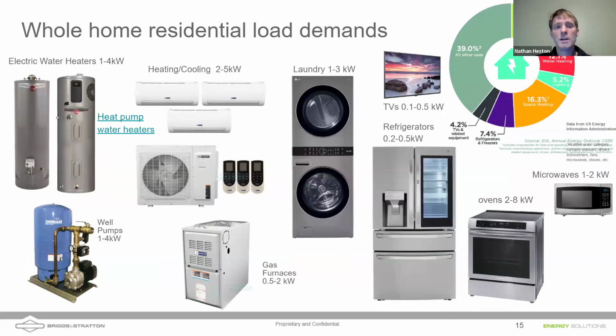cooling with electrical. The advantage of a heat pump as opposed to resistive heaters with electrical is you're moving about 3 times the amount of energy for the same amount of power draw, right? You can get a high coefficient of performance with them. I point out electric water heaters in the top left. These are typically devices that use 2 or more kilowatts, maybe 1 kilowatt with a small resistive electric water heater. Heat pump water heaters offer some advantages.